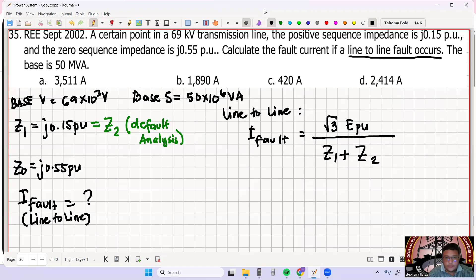Okay, so therefore your I fault now is equal to square root of 3 multiplied by E per unit, which is 1, all over J.15 plus J.15. So square root of 3 multiplied by 1 all over 0.15i plus 0.15i. This is now equal to negative J, 5.774 per unit.